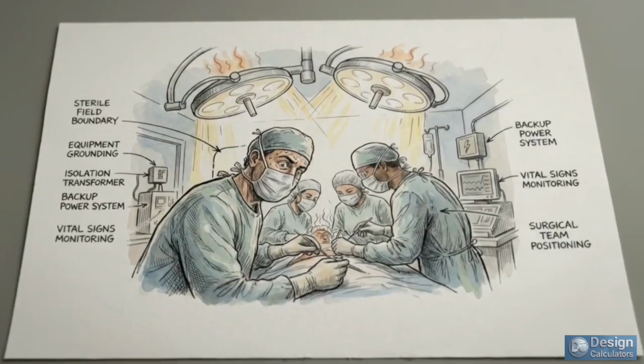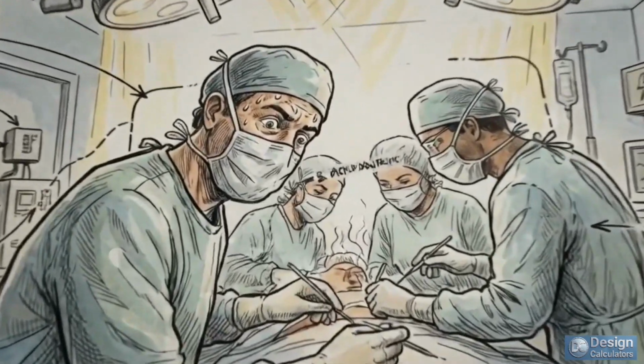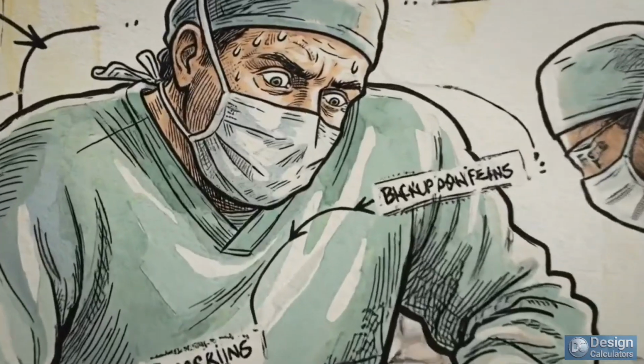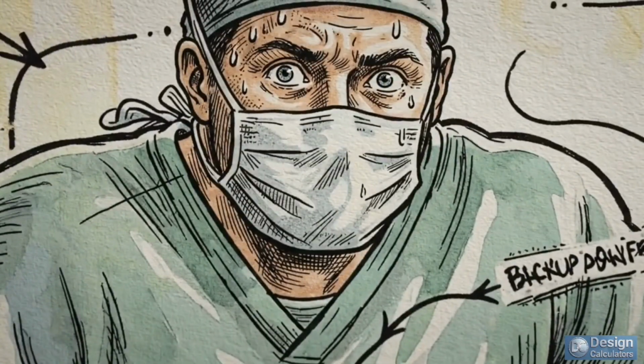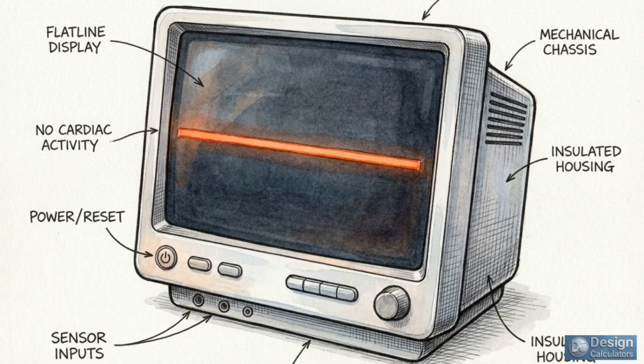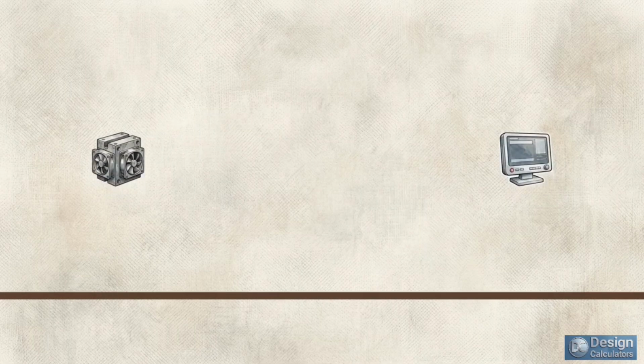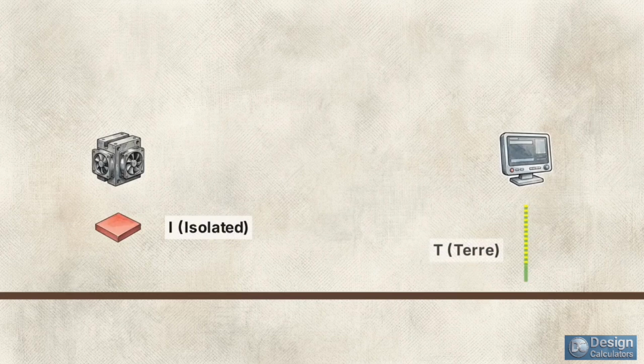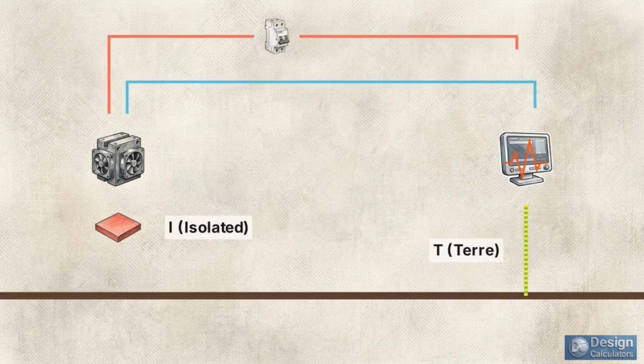In a hospital operating room, an automatic shutdown is a critical hazard. Cutting power to life support or surgical lighting can be just as deadly as an electric shock. These zero-fail environments use the IT, or isolated terre, system. In this schematic, the main power source is either completely detached from the earth or connected through massive electrical impedance. Meanwhile, the medical device maintains a separate ground connection.